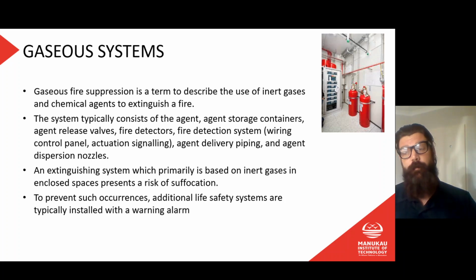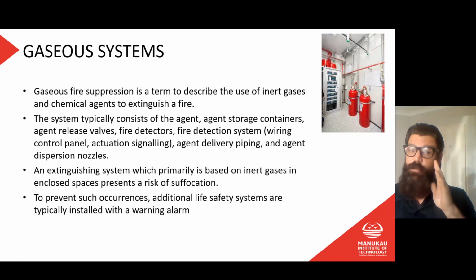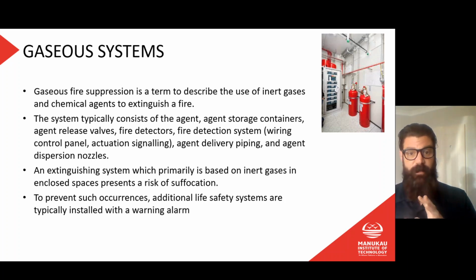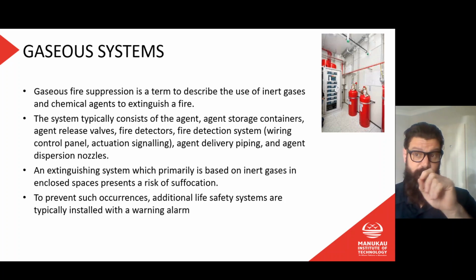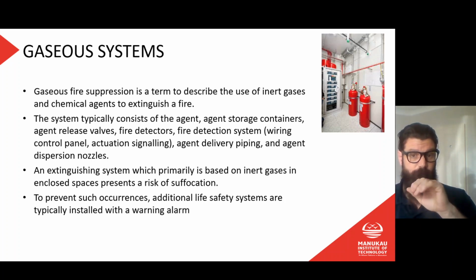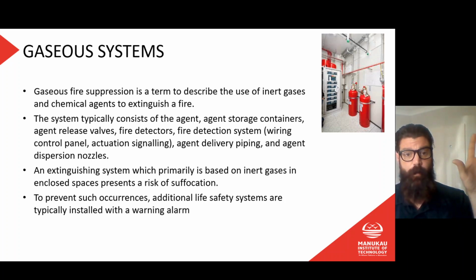So an alarm will go off, and usually it'll be a spoken voice alarm, and it'll say fire, please evacuate the building, the gas system is about to go off, and it might have a countdown until that gas system goes off. If you hear that, you need to be out of that building, because once it goes off there's no stopping it. The valves are usually like a detonator, so they actually fire. You can't reset them, you can't turn them off. Once that detonator goes and fires that valve open, it's destroyed. So all of the gas is coming out all at once, and there's no way to stop it, so you need to be out of that space.